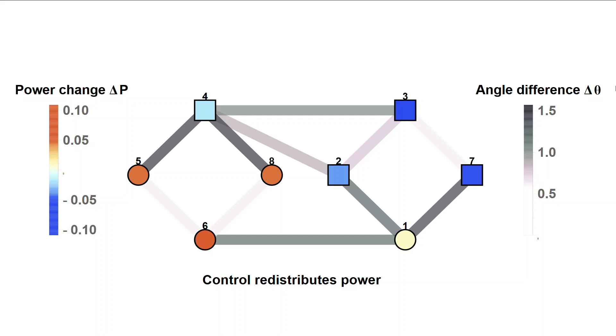In this example, the network would overload without control. The added control reduces the amount of consumed power by some nodes and increases the consumed power in other parts of the network, thereby shifting the flow away from the critically loaded lines.